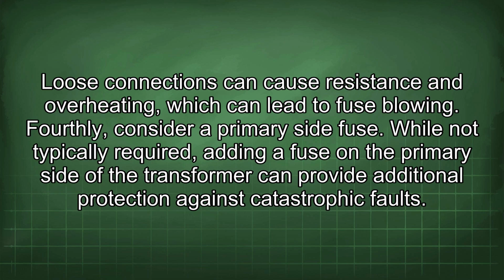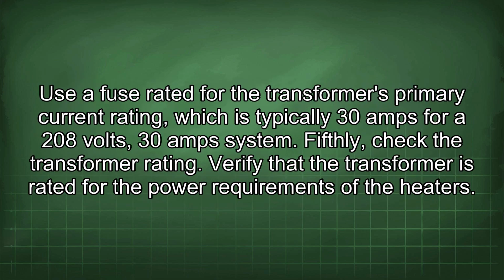Fourthly, consider a primary side fuse. While not typically required, adding a fuse on the primary side of the transformer can provide additional protection against catastrophic faults. Use a fuse rated for the transformer's primary current rating, which is typically 30 amps for a 208 volts, 30 amp system. Fifthly, check the transformer rating.